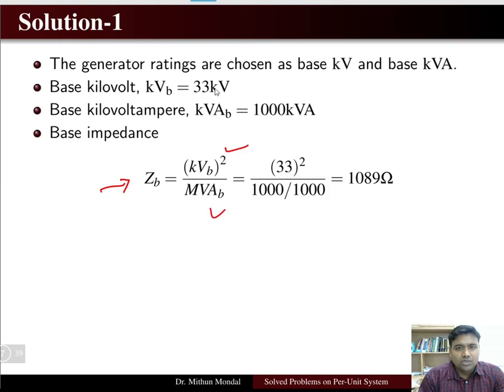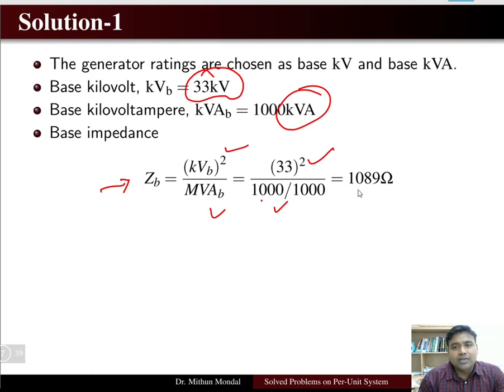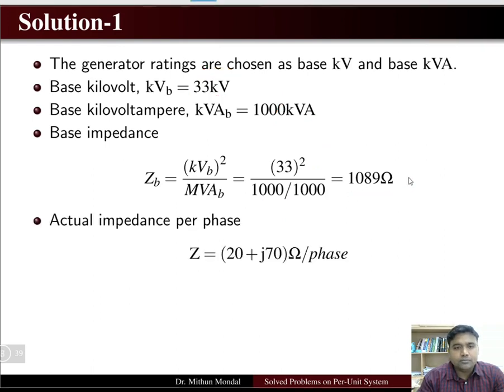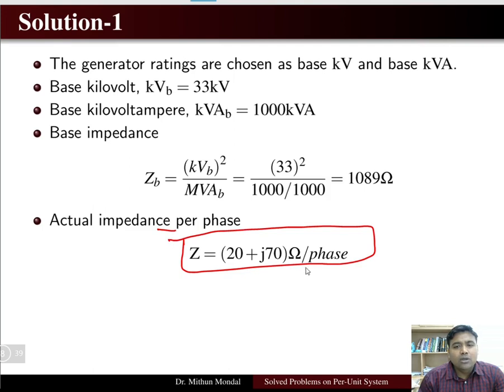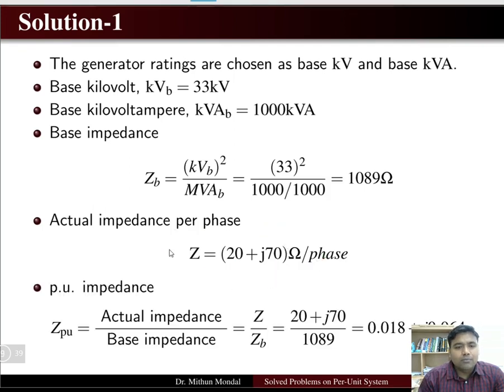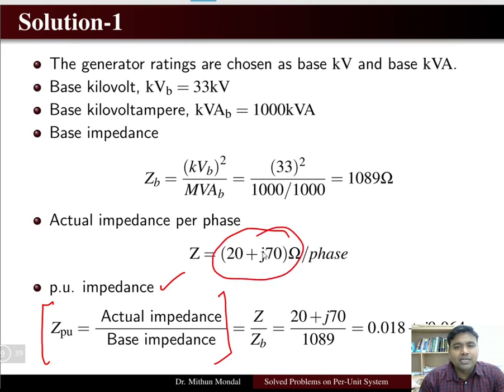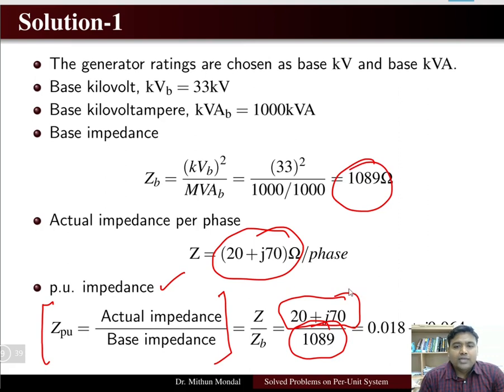The base impedance formula gives us kV base squared divided by MVA base. With kV base = 33 kV and MVA base = 1 MVA (converting 1000 kVA), the base impedance is 1089 ohms. The actual impedance per phase is 20 + j70 ohms. The per unit impedance equals actual impedance divided by base impedance, giving (20 + j70) / 1089. Note that the actual value is a complex quantity but the base value is always real.